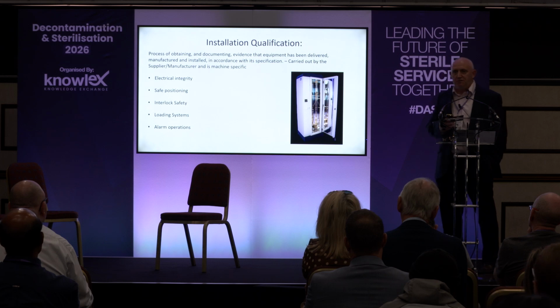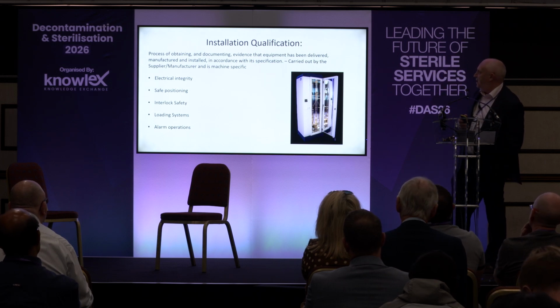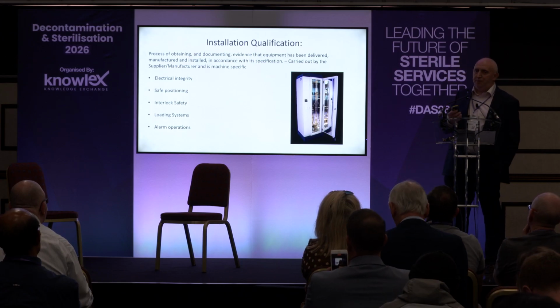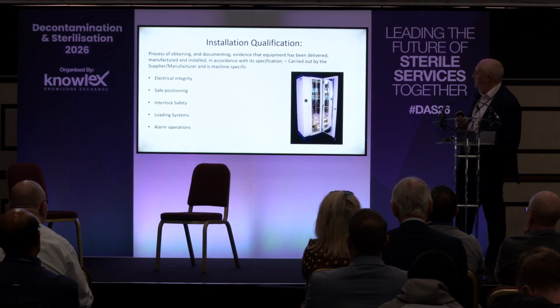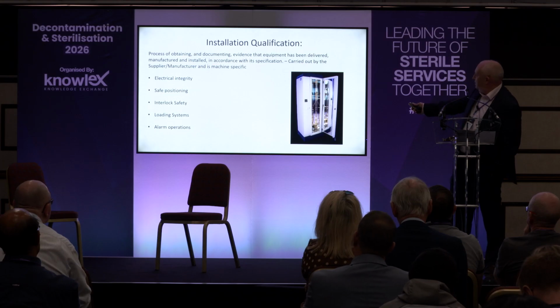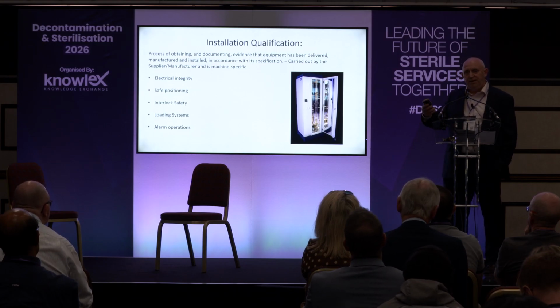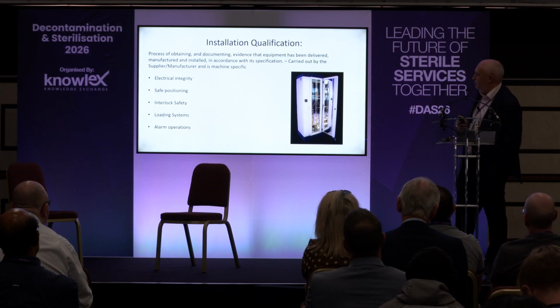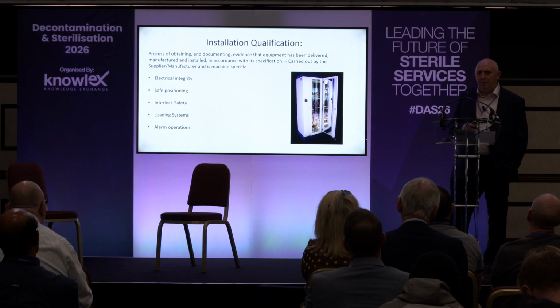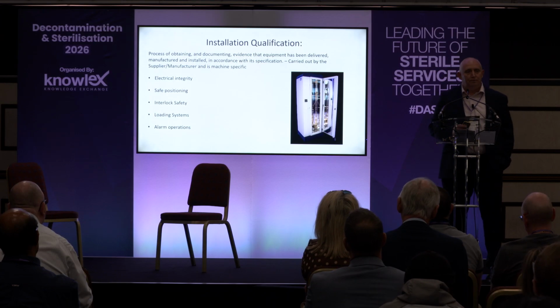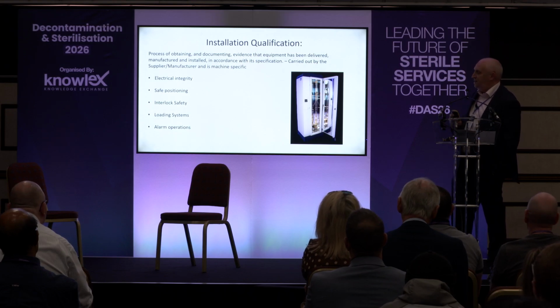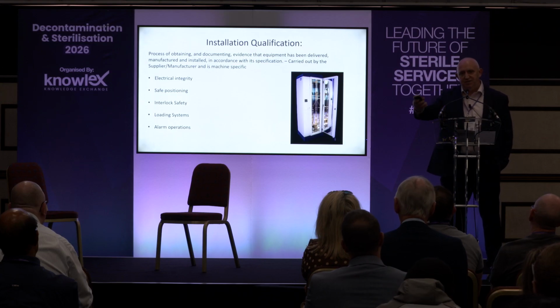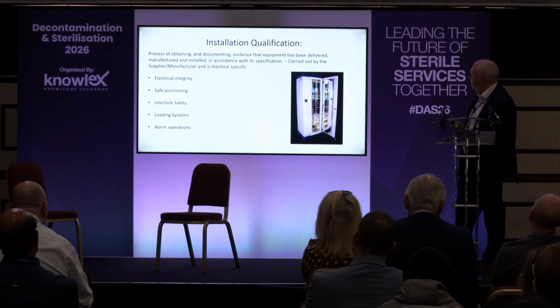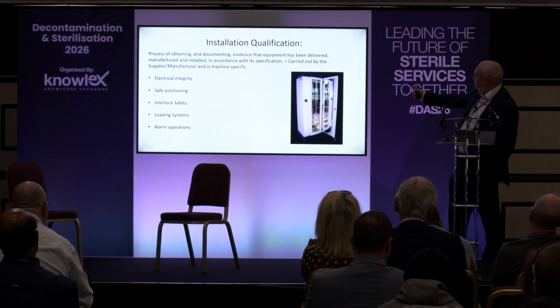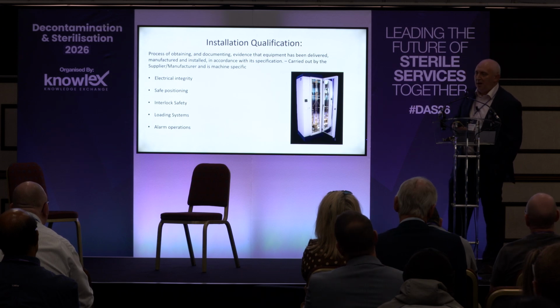Then we have the installation qualification, typically done in what they call commissioning, carried out by the supplier, the manufacturer. So this will confirm the electrical integrity of the system. It will confirm the safe positioning. So if you look at that, that particular machine is taller than me. So it's got to be in a safe place, securely bracketed, etc. Those are the things that we cover during the IQ process. Interlock safety, yeah, we've talked about UV being a harm to staff. We don't want that door suddenly becoming open during a cycle. So we need to make sure of that. We need to make sure the loading systems are robust. It recognises when a device is inserted and it recognises when the device has been removed. And it has to have the correct alarm operations for that particular design, because each design will have a little bit of variability.